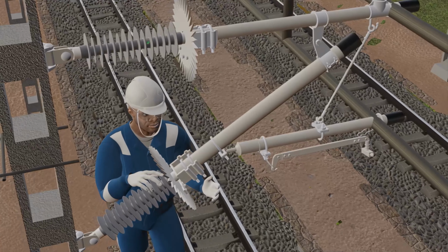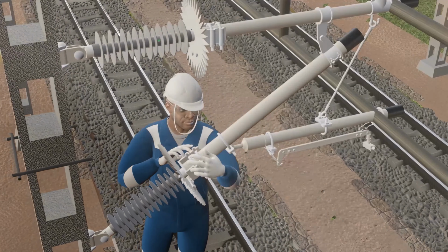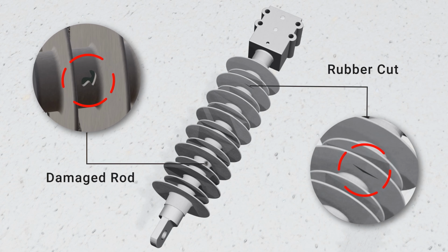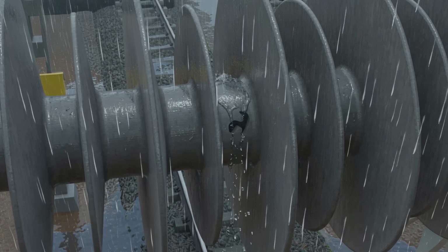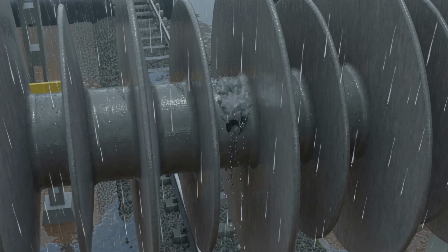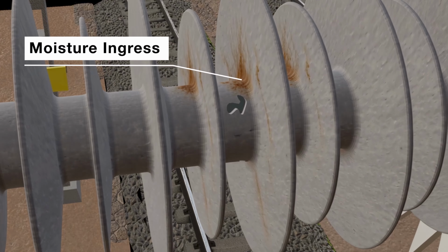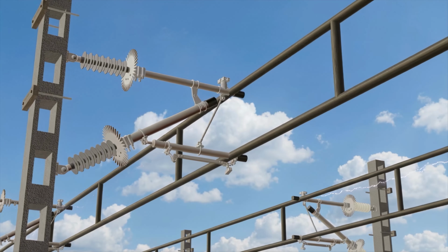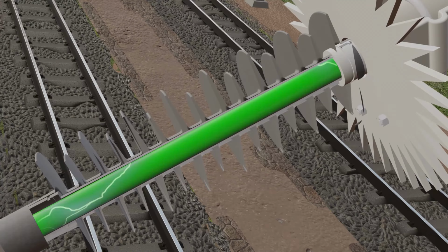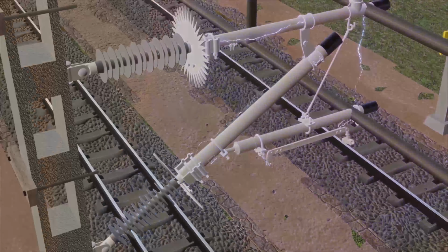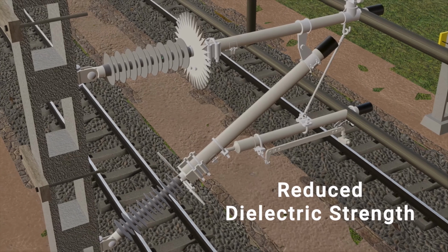If the following instructions are not followed, serious failures can occur. When the rubber housing is cut and the core is exposed, moisture can enter during rainfall and penetrate the core rod and silicone rubber interface. Moisture ingress is a critical failure mechanism that progressively degrades both the electrical and mechanical strength of composite polymer insulators. First, reduced dielectric strength. Moisture increases the dielectric constant and dielectric loss of the silicone rubber or epoxy rod interface. As a result, insulation resistance drops significantly, weakening the overall dielectric strength of the insulator.